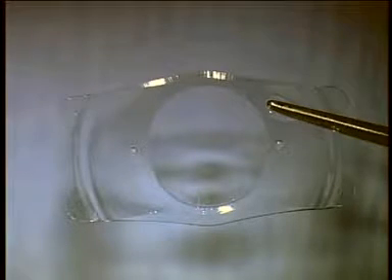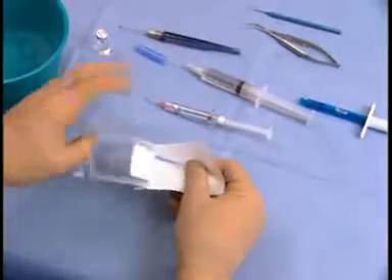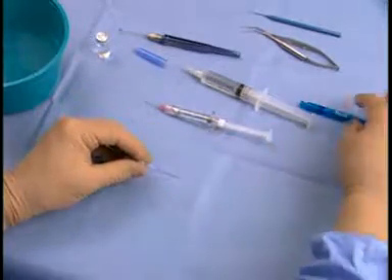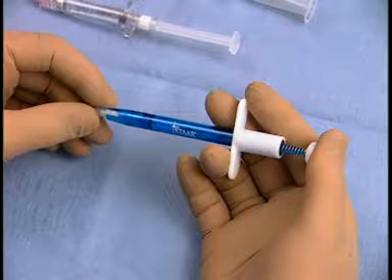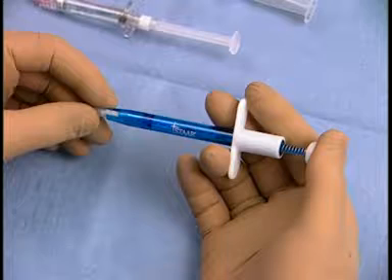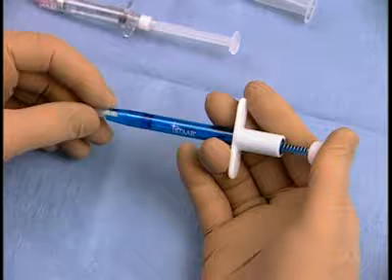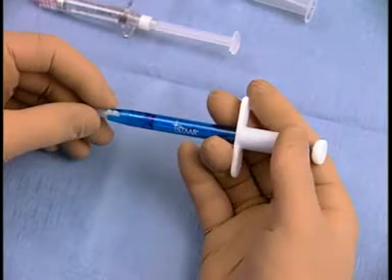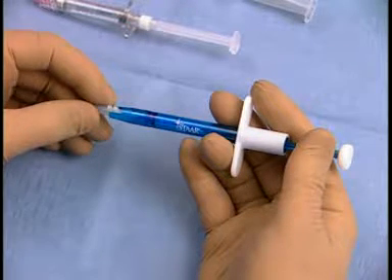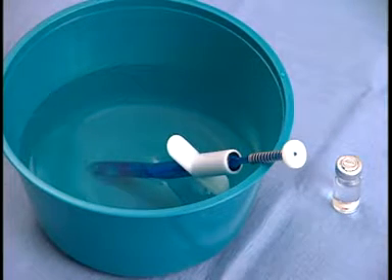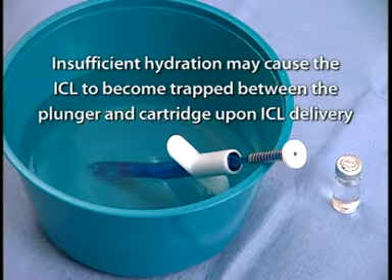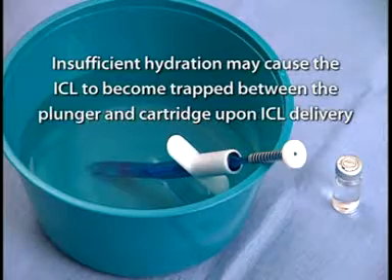The Star ICL is made from Collamer, a hydrophilic collagen copolymer. To begin, remove the foam-tipped plunger and holder from the package and insert it into the injector, base first. The vertical tab of the holder is not intended to be snap-locked into the notch of the injector. Advance the injector cap until the ball end of the plunger interlocks with the injector — a click can be felt and heard when the plunger is properly secured. Retract the injector plunger fully and remove the holder. Place the assembled foam-tipped plunger and injector into BSS, ensuring the tip is completely submerged. Hydration of the foam-tipped plunger is extremely important, as insufficient hydration may cause the ICL to become trapped between the plunger and cartridge upon ICL delivery.